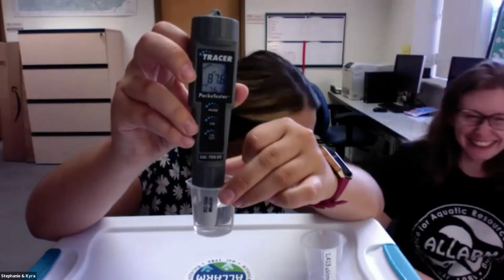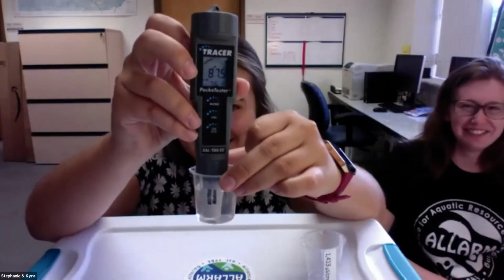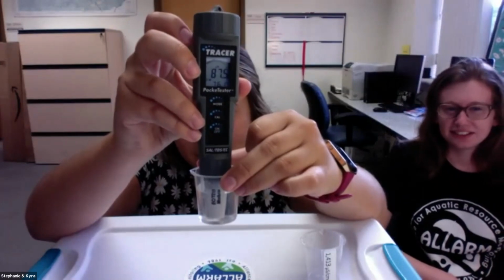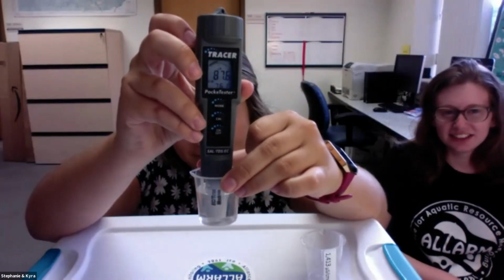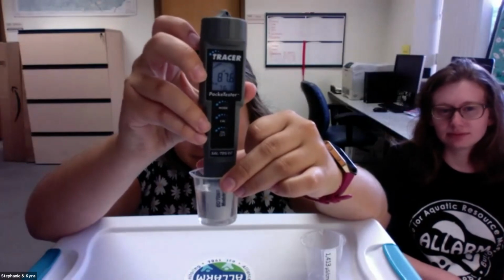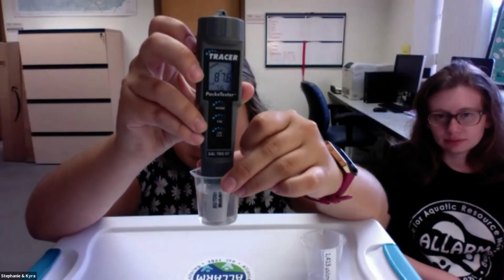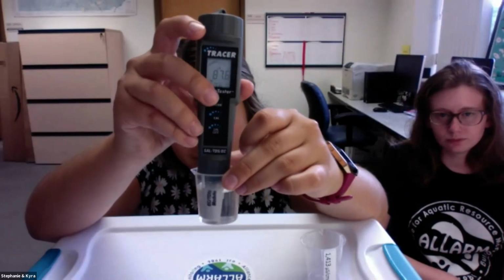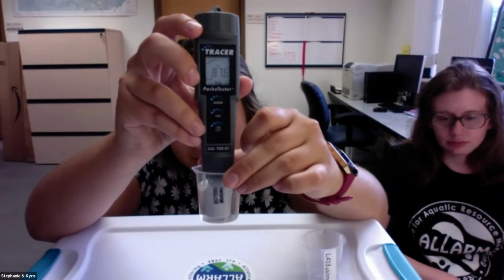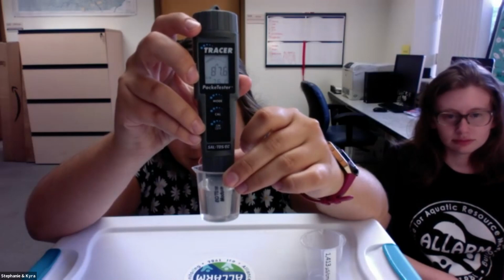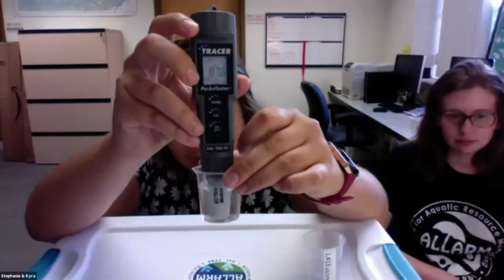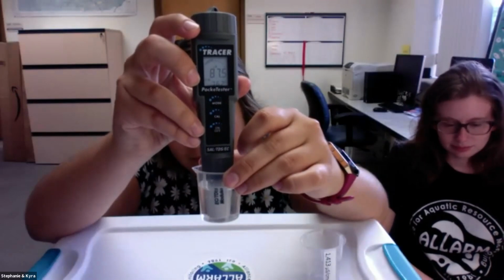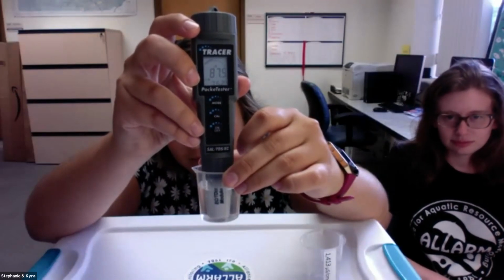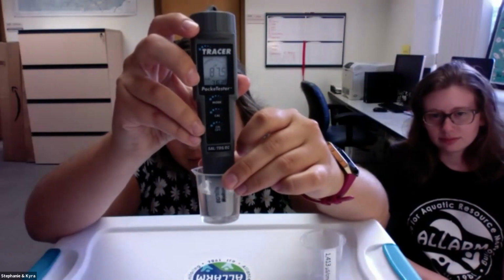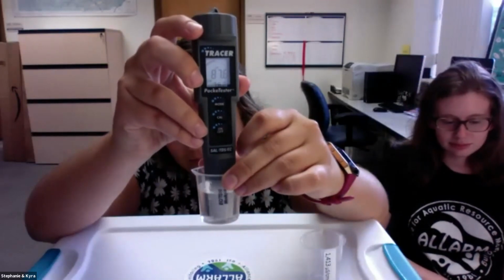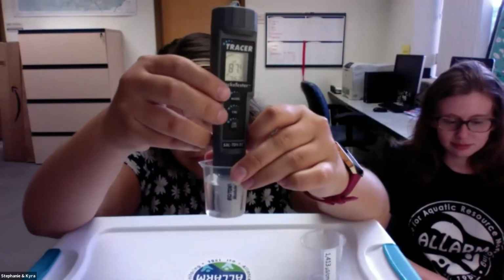So Stephanie, I believe your value has begun to stabilize. So if we look at the screen, I am going to ask everyone to look up and watch Stephanie do this before you do it on your own. As you can see, Stephanie's conductivity value is stable at 87.6. I'm going to read the whole directions and then I'll walk her through it. You're going to press and hold the calibration button for approximately 2 seconds until cal appears on the bottom of the screen and 84 flashes. At this point, you release that button.